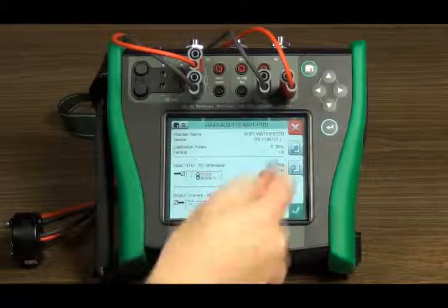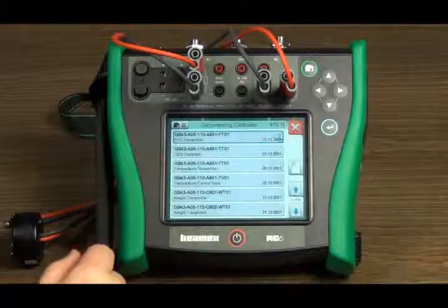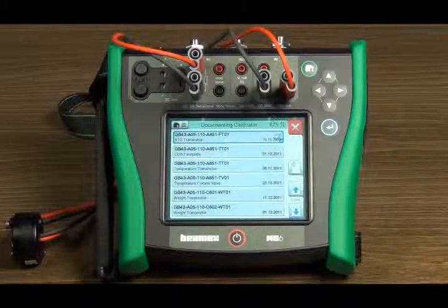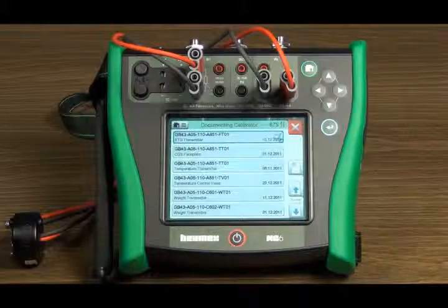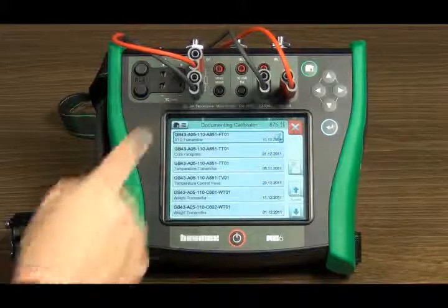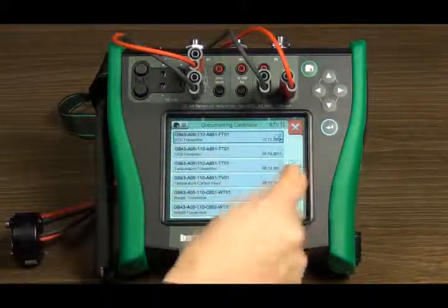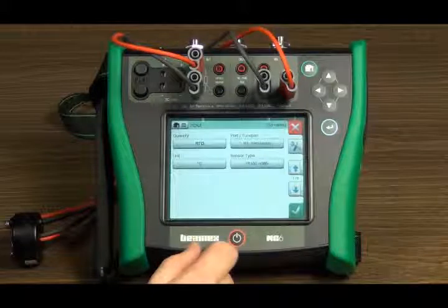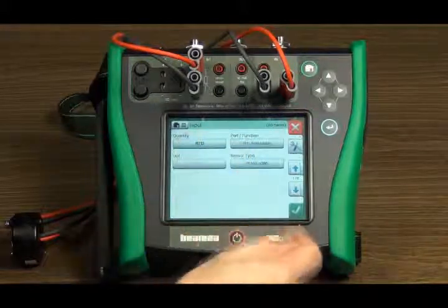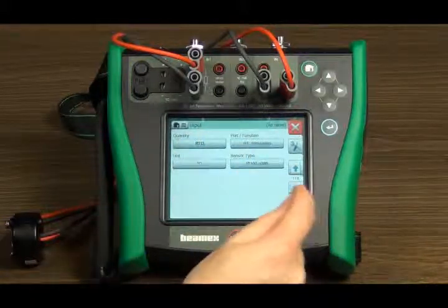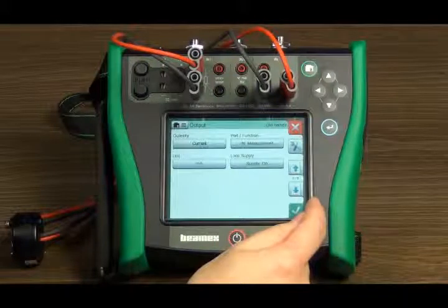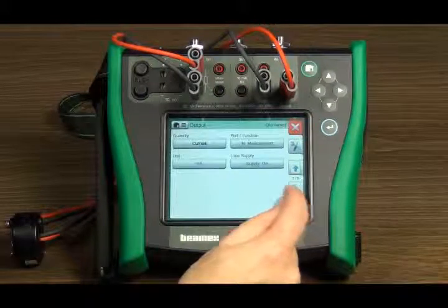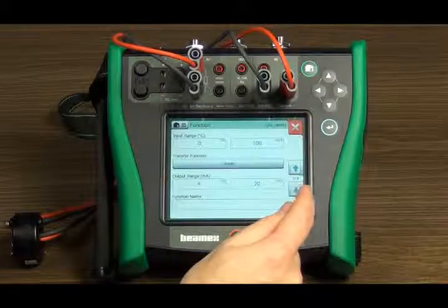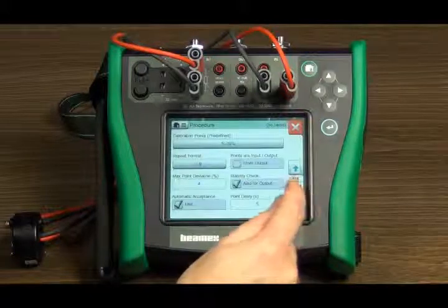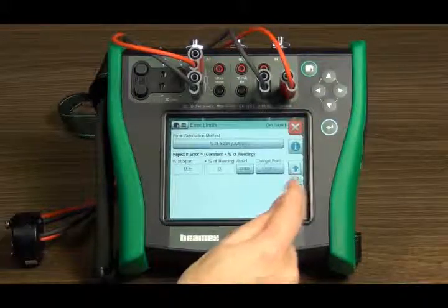You can send new instruments to the calibrator's memory from the calibration management software. You can also create new instruments in Calibrator. It can be done via the menu or by touching the Create New icon in the instrument list. To create a new instrument, you will need to fill in a few pages with the information about the instrument. These pages contain information about the instrument input, output, function, procedure, error limits and identification.